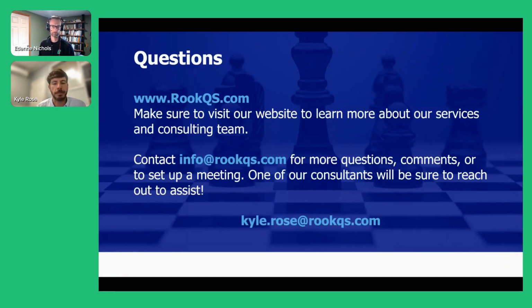How to define that acceptance would really be in your plan and tie specifically to your device and what the risk profile is, right? Class 1 is going to be different than a class 3. So it would have to take in specifics for each device. But the key aspect is going through everything once all the testing is complete and all the design features are complete, to see which residual risks were reduced and which ones still might be high. And that's just a known thing. And you need to go to your benefit risk analysis to see if you can release that product. So it's a lot of being close to the product, but the formal documentation of that should be done.